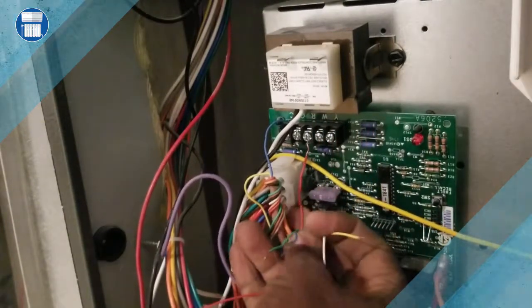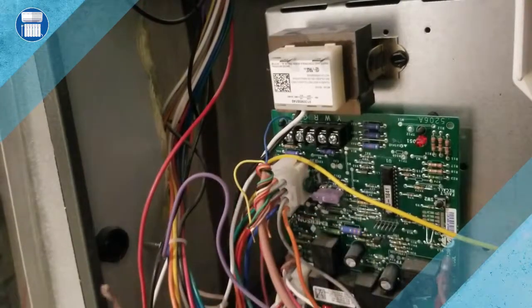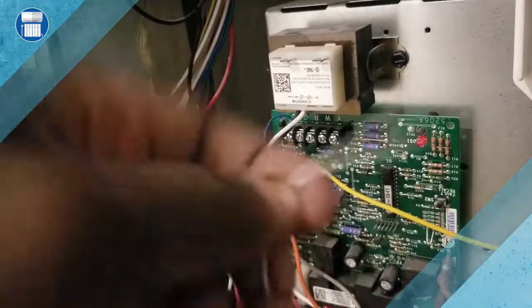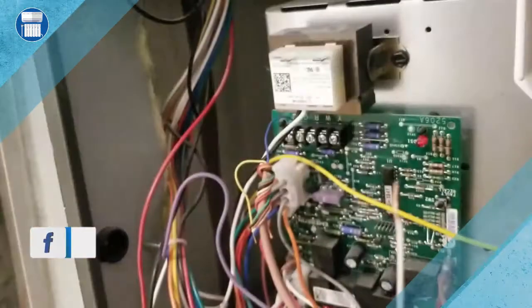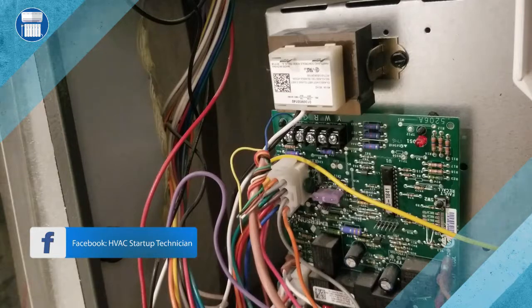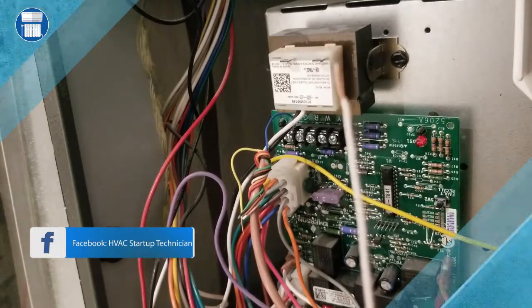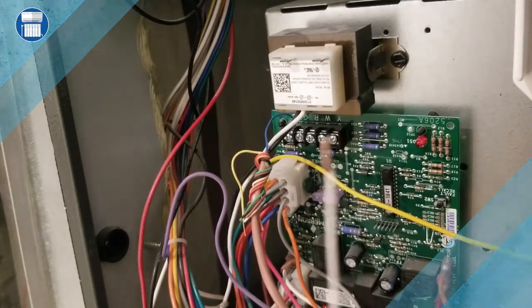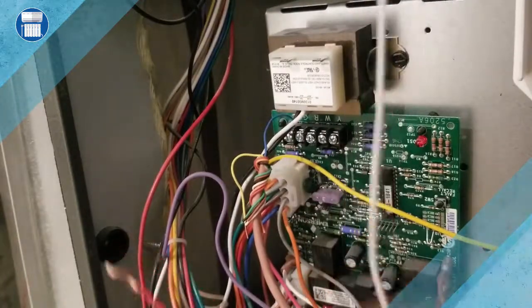We're going to put that to your R terminal right here. Then we're going to white, which is for heat. If you have to jump your unit and your heat is not working, that's when you normally put a jumper between red and white. So this white wire here is going to go to your W terminal, which says white.